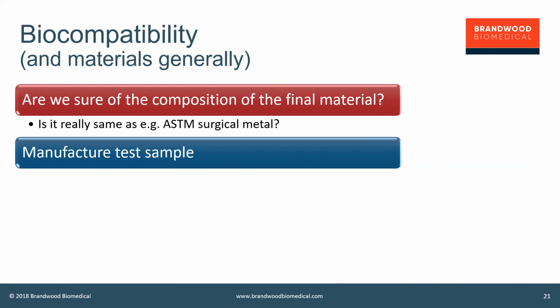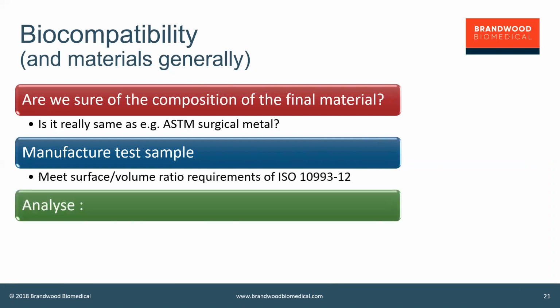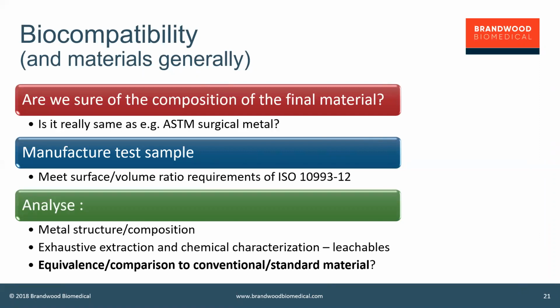doing an extract. And the Part 12 standard in ISO defines the volume to surface area ratio of the test sample that you immerse in the test solvents to do an extract. So 3D printing is great because you could actually print test samples that provide you with the right volume surface area ratio to make it easy. So you can print your test coupons using your additive manufacturing machine. Manufacture the test sample, meet those surface to volume ratio requirements, and then analyze it. Do metallurgy if necessary to look at the final structure of the metal, and do exhaustive extractions and chemical characterizations.